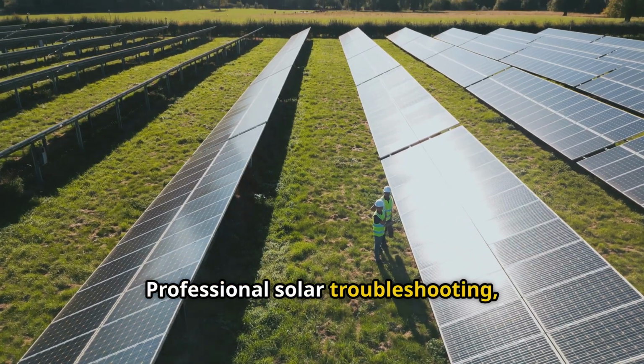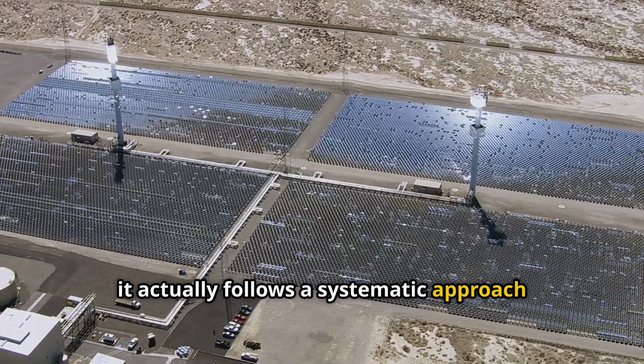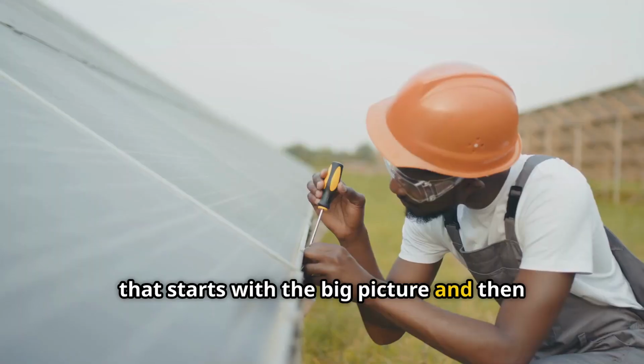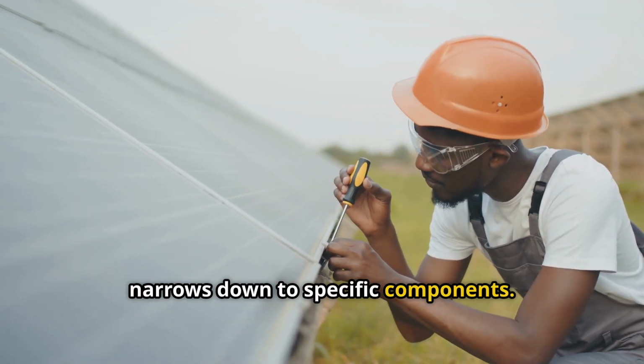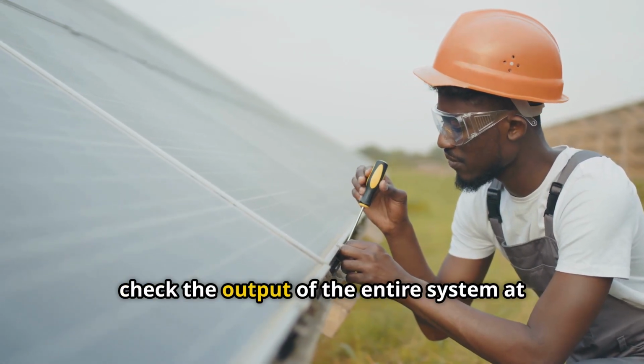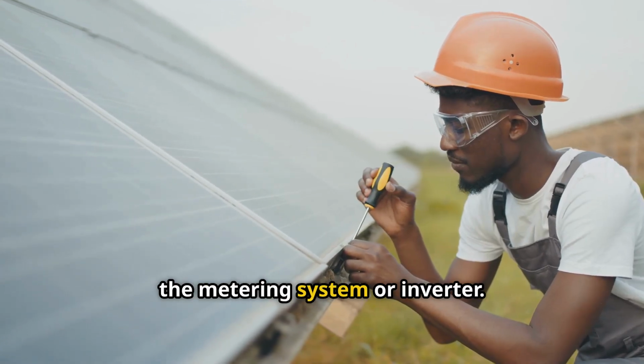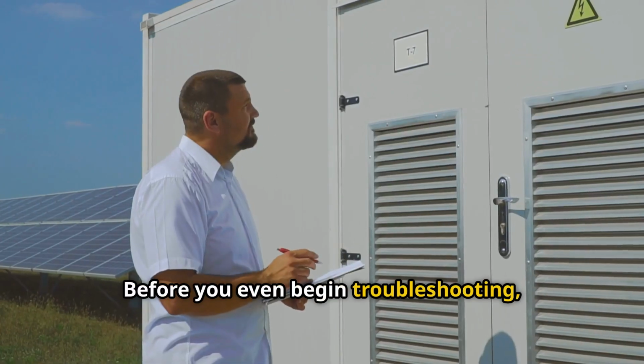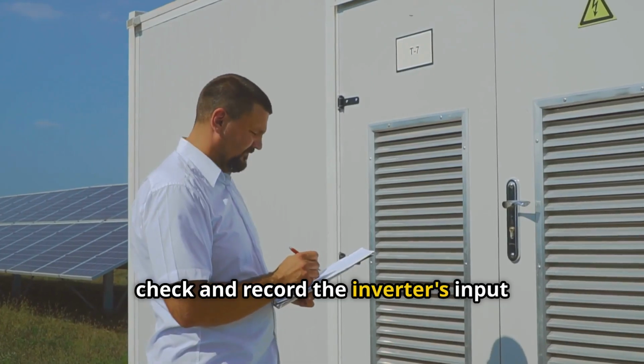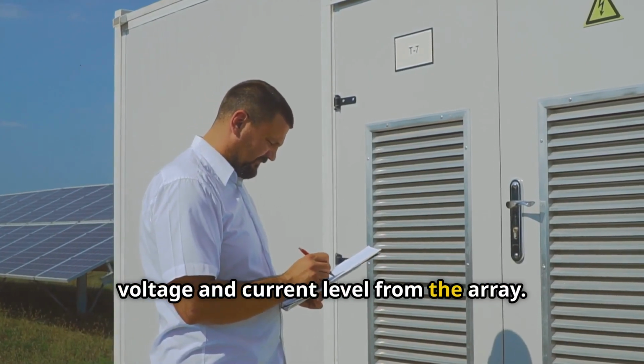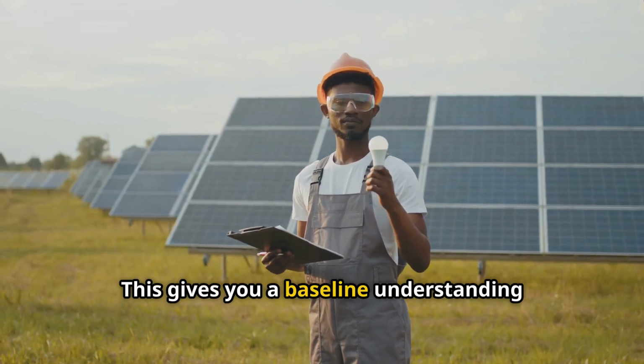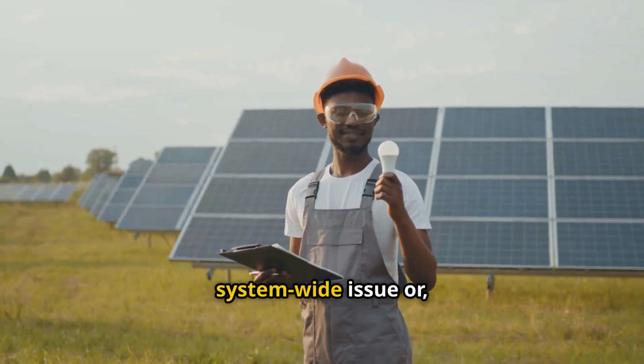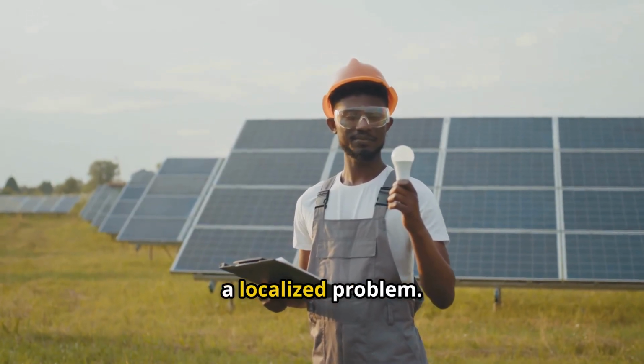Professional solar troubleshooting follows a systematic approach that starts with the big picture and narrows down to specific components. First, check the output of the entire system at the metering system or inverter. Before you even begin troubleshooting, check and record the inverter's input voltage and current level from the array—this gives you a baseline understanding of whether you're dealing with a system-wide issue or a localized problem.